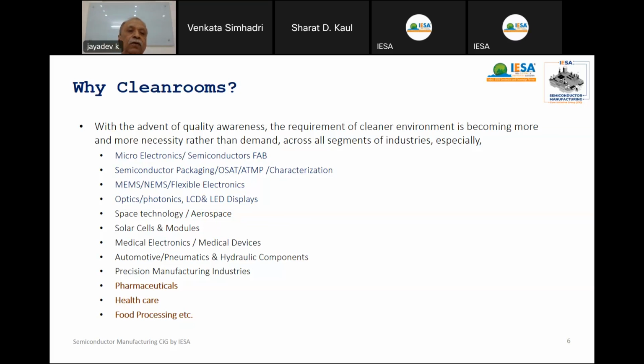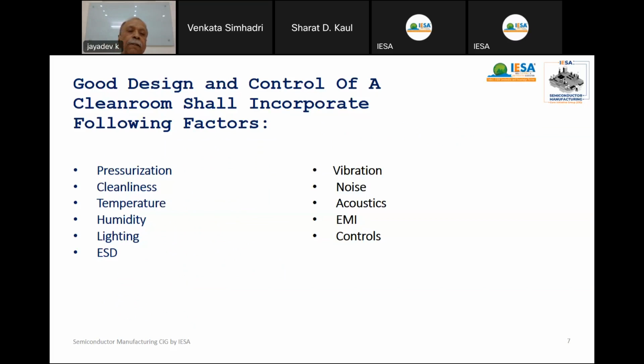Okay. Now we'll move next. A good design of a clean room control will incorporate the following factors. One is pressurization, cleanliness, temperature, humidity, lighting, electrostatic discharge. In special cases, vibration may be required, noise control is required, acoustics is important, and electromagnetic interference controls. We'll discuss more on pressurization, cleanliness level, temperature, humidity, lighting, and ESD.